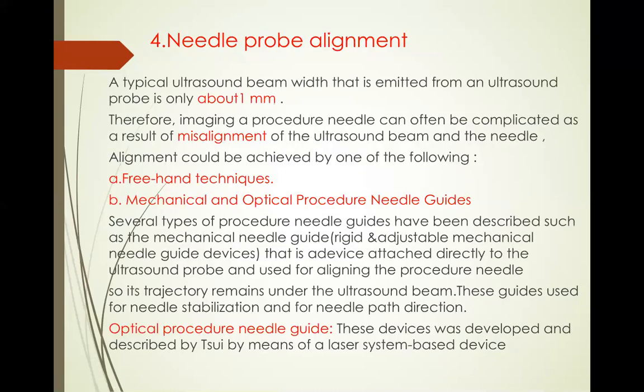The needle probe alignment: a typical ultrasound beam width emitted from an ultrasound probe is only about 1 millimeter. Therefore, imaging the procedure needle can often be complicated as a result of misalignment between the ultrasound beam and the needle alignment.